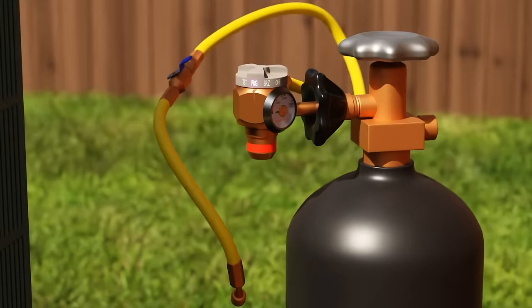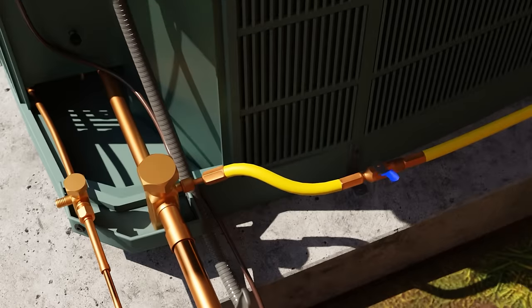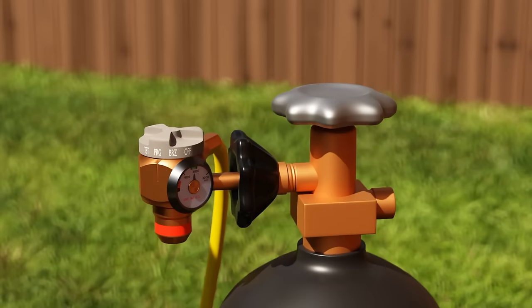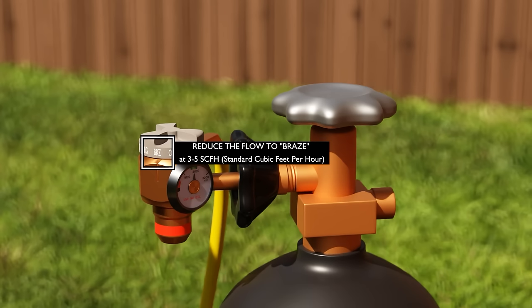Next, we purge the air from the system. Then we move it to brazing mode, or what we call flowing nitrogen while brazing, which flows a very slow amount of pressure, 3 to 5 SCFH, or standard cubic feet per hour.